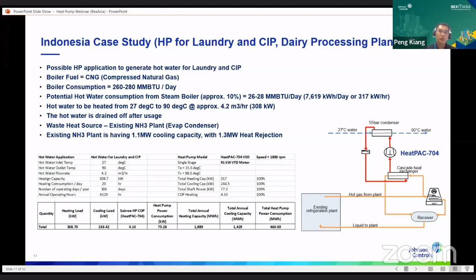So we are using some waste heat source from the ammonia condensers to generate this kind of heating. And through the COP of the heat pump, which is about 4.1 in this case, when we select the heat pump, we have some annual heating capacity and also annual cooling capacity we can extract from the existing ammonia plant and produce some sort of heating for that. So with this annual consumption of heating and cooling at the same time, we can also work out the equivalent CO2 and also the energy consumption from the boiler and the fuel consumption from the boiler, right?